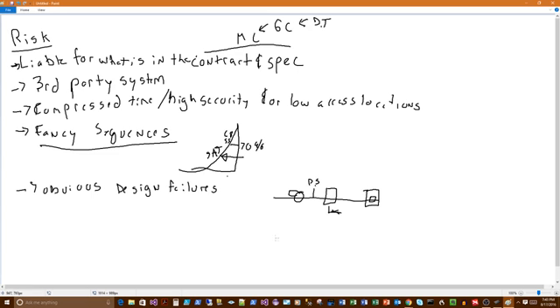Or maybe you see something like this: a DX unit with two stages of cooling and a fan with a VSD on it. Then you ask yourself, how exactly am I going to control staged DX cooling with a VSD unit? I've seen it done in the past using bypass dampers, so you always had the right amount of air over the coil so it didn't freeze.